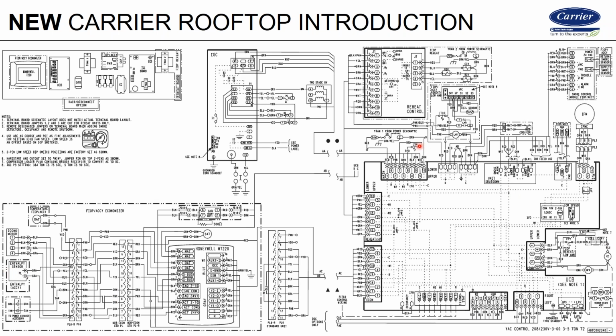Here we got red wires, so I'll use a red laser. So that limit is right here. And if you were to follow and trace this all out, it ultimately ends up right back here at the transformer. So if that limit on the side of the blower housing trips, we're killing power right off the transformer. And in turn, that's shutting power down to what we call the IGC board, which I'm going to get into more detail on in a minute. That's your integrated gas controller. It's going to control your fan control and auto, your gas valve, all those things.